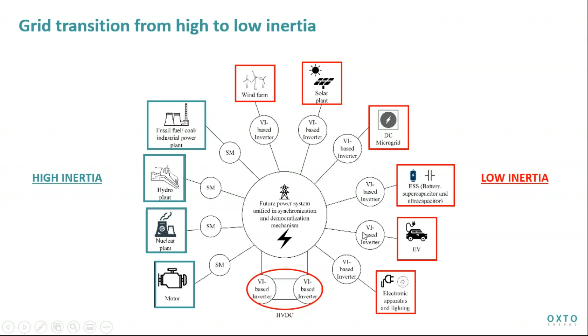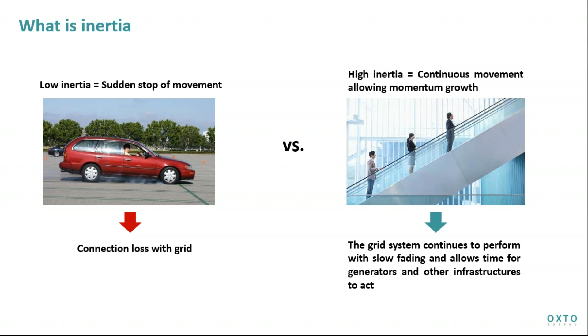As Mark already described, what's important with inertia is that with high inertia you get a fading effect, whereas with low inertia it's more like falling off a cliff. This makes a big difference for the grid, because there's no time to react without inertia, and that's a major issue.